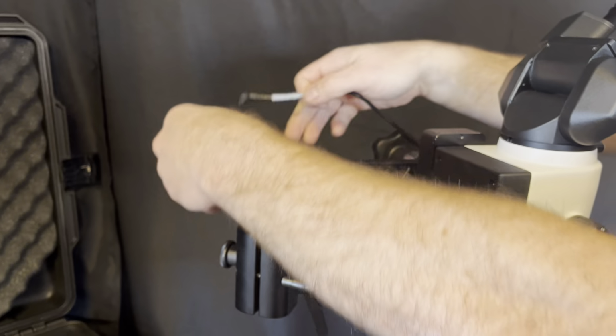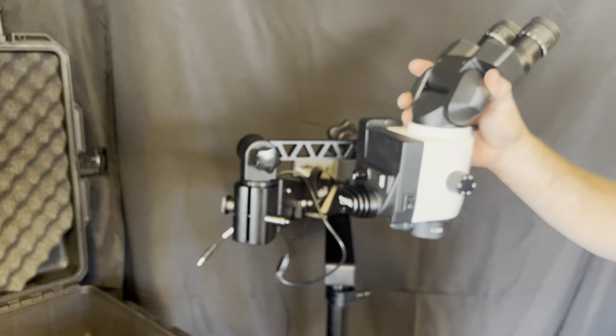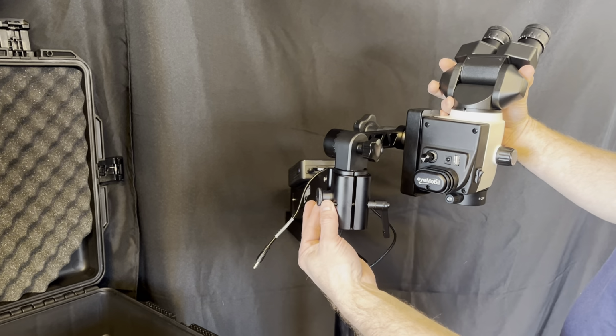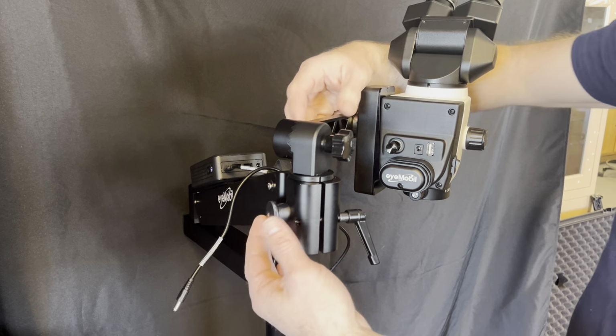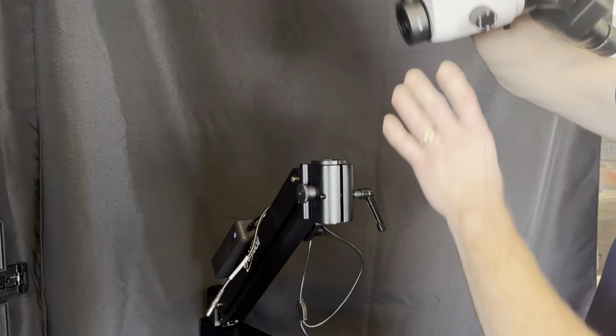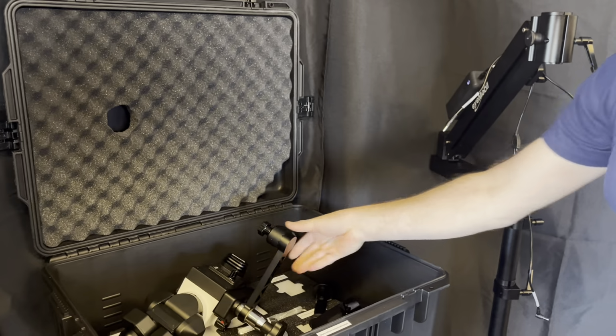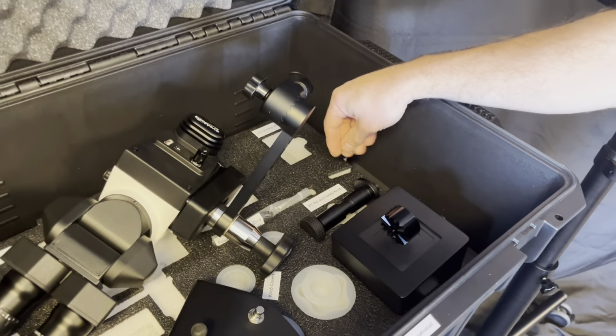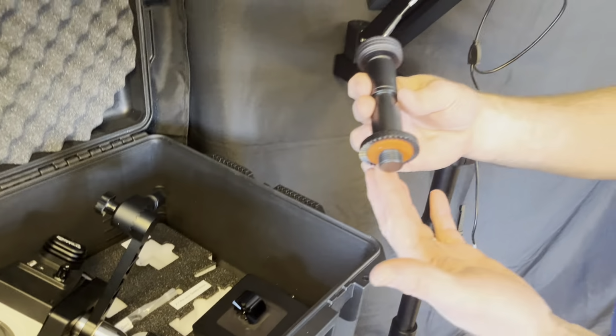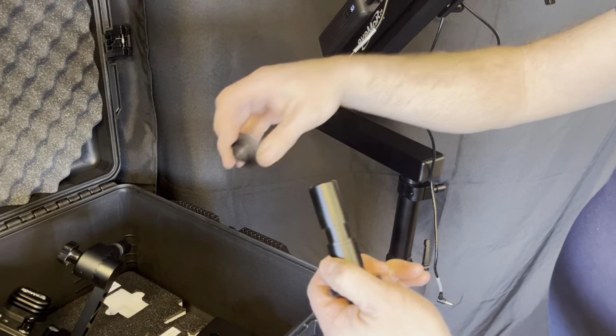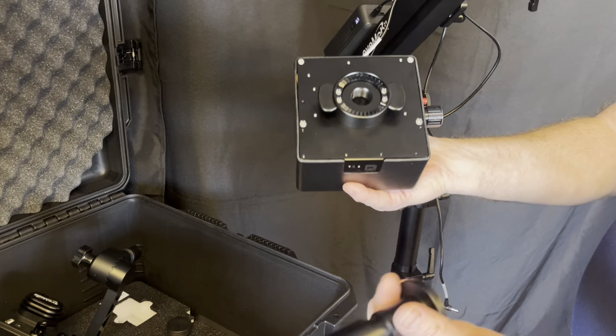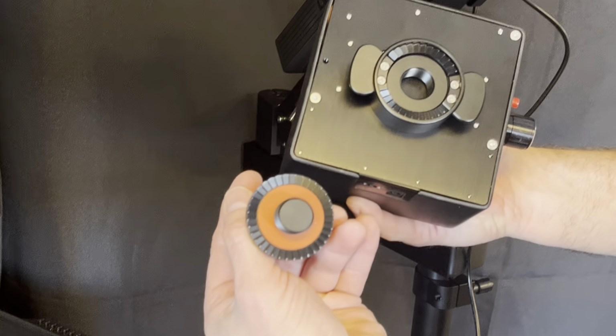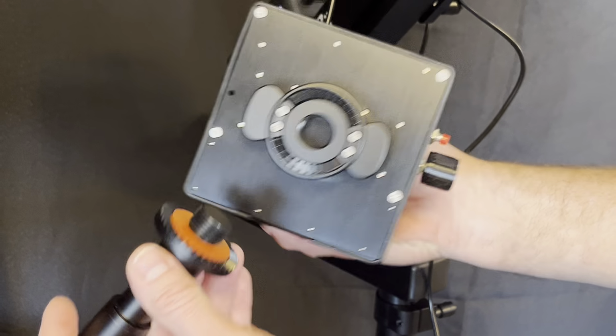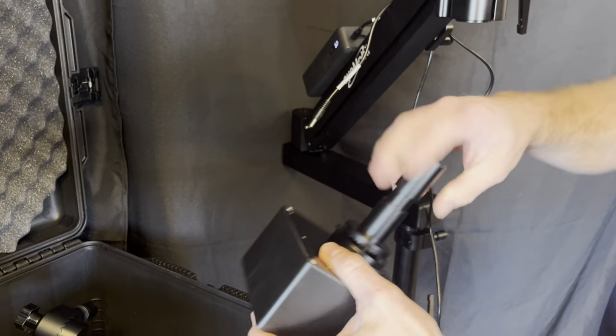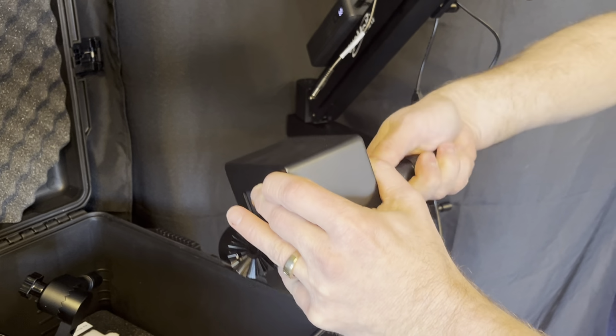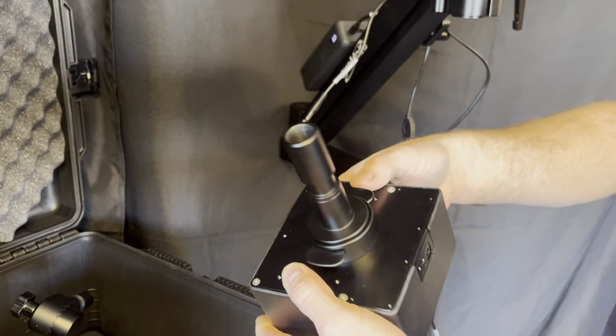So we'll want to disconnect the battery cable from the head of the microscope in order to be able to change the configuration. The mini index plunger has to be pulled and the tension handle loosened to remove the microscope from the flex arm. In the bottom layer of your case is the XY unit, along with the pin and safety knob. So we'll take out the XY pin, remove the safety knob, take out the XY unit and turn it over. You can see how this post threads into the receiver on this side of the XY unit. It's a very easy thread to turn in. It will begin to ratchet, and you just tighten it until the ratcheting stops, and then it is secure.